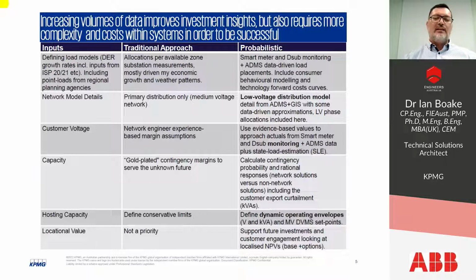That's a system that really has a lot of visibility around the real-time flows of power and voltages, etc., on the medium voltage network, but not so much visibility around the low voltage network. So most of them have a fairly comprehensive network model, and that network model is a geographical information system model, and this allows them to actually see when there's an outage, how many customers are affected, to contact them and to resolve the issue as quickly as possible. Traditionally, there was not that level of visibility down to the LV.